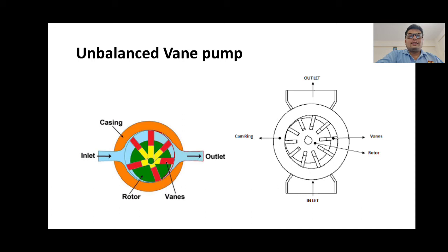In practice, vane pumps have more than one vane, as you can see here, the yellow and red colored. The rotor is offset within the housing and the vanes are constrained by a cam ring as they cross the outlet and inlet ports. Although the vane tips are held against the housing, still a small amount of leakage exists between the rotor faces and body sides. The vanes compensate to a large degree for wear at the vane tips or in the housing itself.